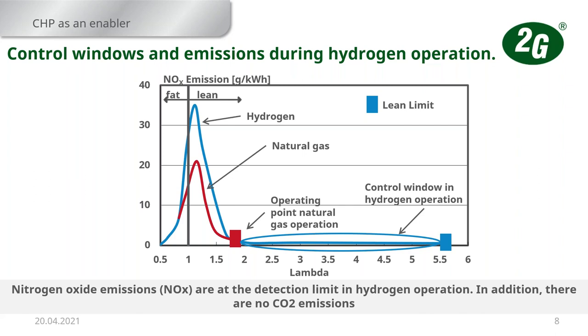When we did the original first engines that we put in on a trial basis, we were running the engines at 500 NOx, because that was quite acceptable at the time, based on the fact that the emissions technology was based on the biogas world. But we've got the engines now running down to 95 milligram NOx, exactly the same engine, with a slight change to the power output. A lot of the applications now are people wanting these engines to go inside city centres, especially running with hydrogen, because of corporate headquarters, etc. So once again, whatever is required for the application, we can play around with the engine tuning and the lambda value to make it achievable.